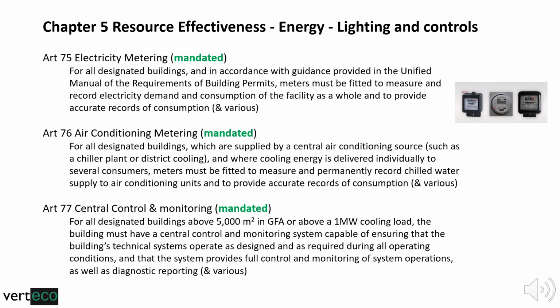Whole building metering is of course mandatory currently as part of EWA's connection to the national grid, and also to facilitate EWA's billing policies. But Articles 76 and 77 provide for not only the sub-metering of large plant and HVAC, but also the mandatory storage of such meters' data logs. As a result, it will be very important that those meters are connected to a building management system, or BMS, also indicated here as a central control and monitoring system. That connection is very important.